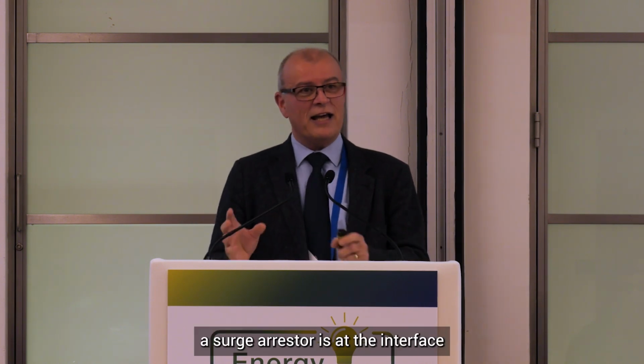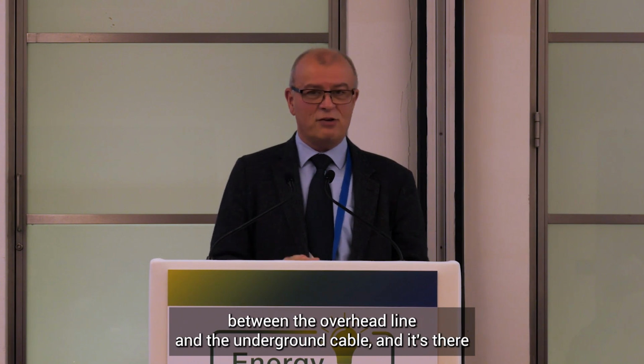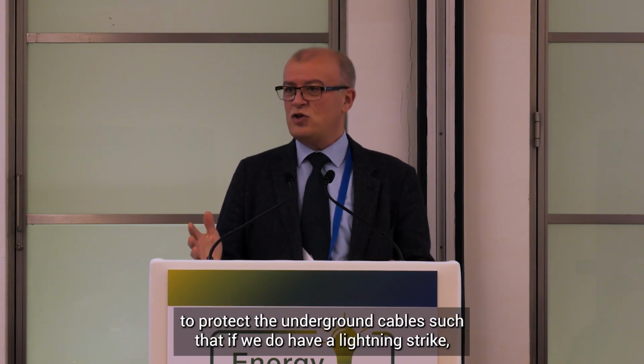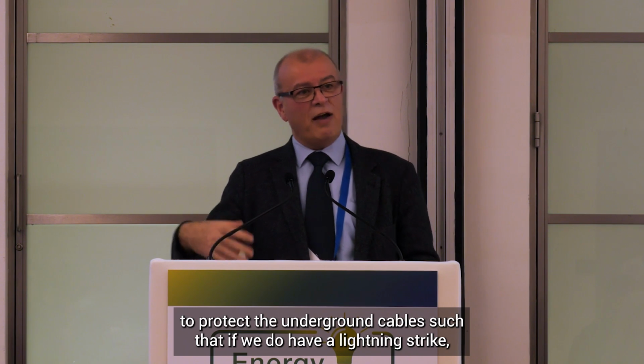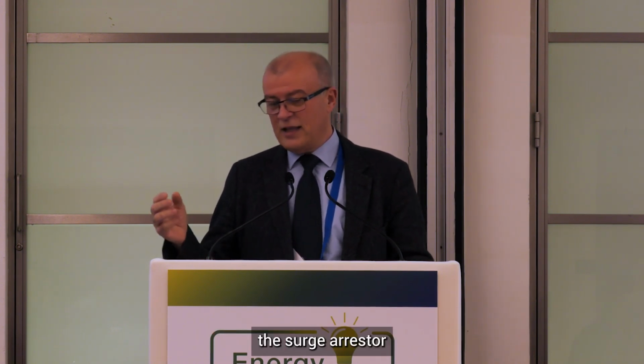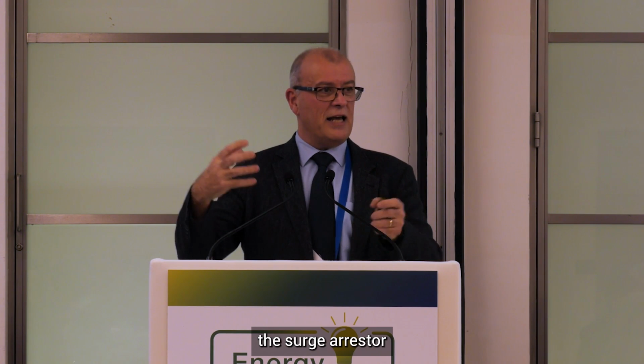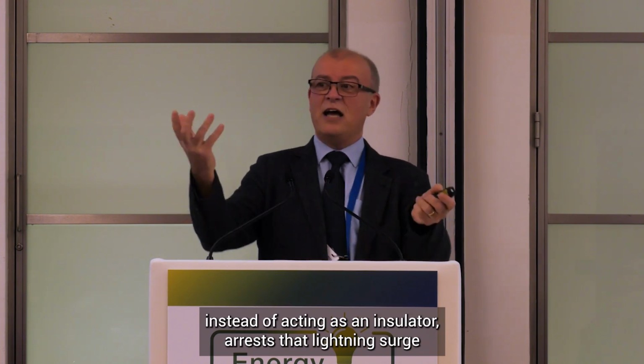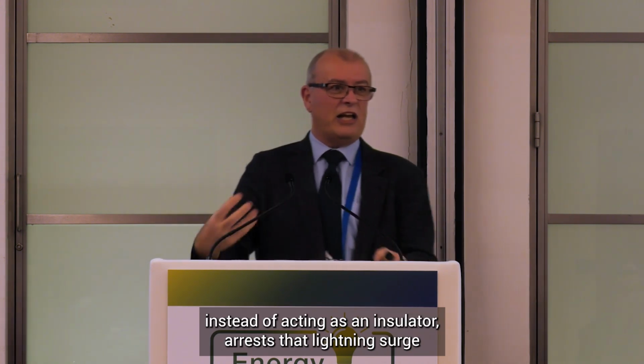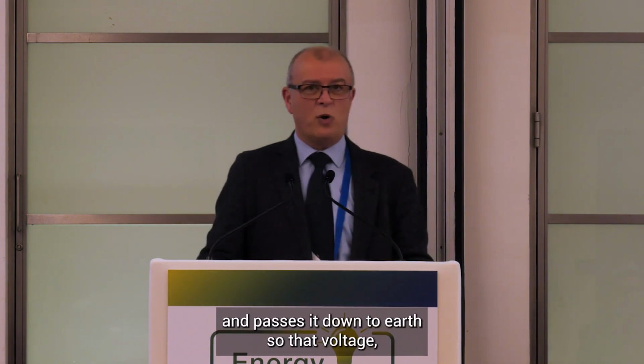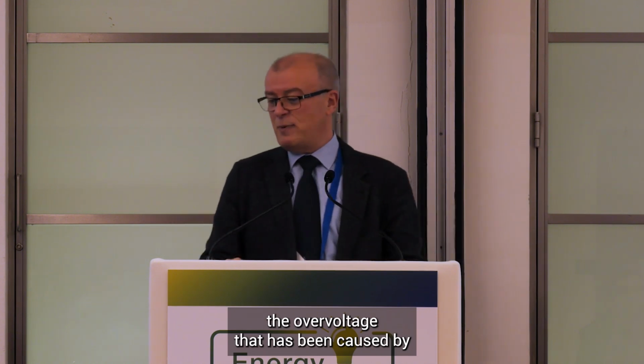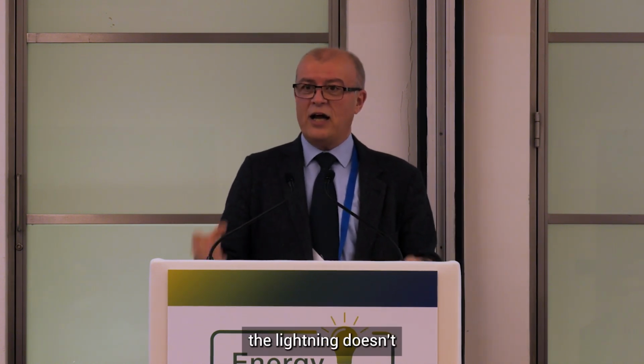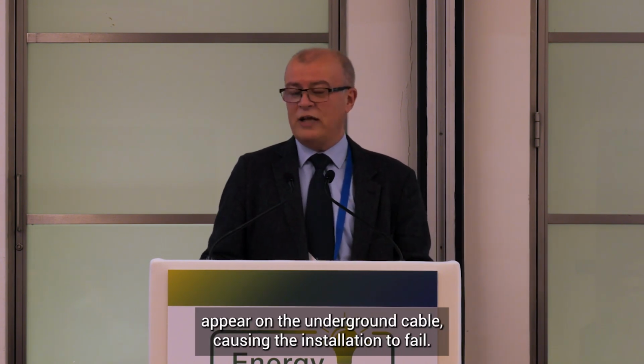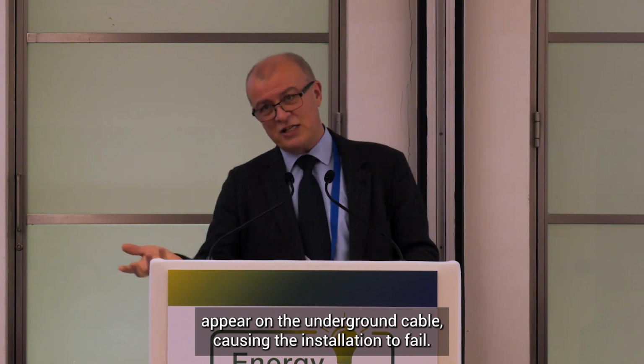A surge arrestor is at the interface between the overhead line and the underground cable, and it's there to protect the underground cable, such that if we do have a lightning strike, the surge arrestor, instead of acting as an insulator, arrests that lightning surge and passes it down to earth, so that the overvoltage that has been caused by the lightning doesn't appear on the underground cable, causing the insulation to fail.